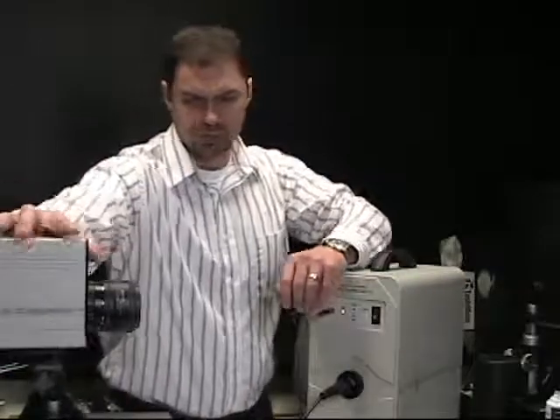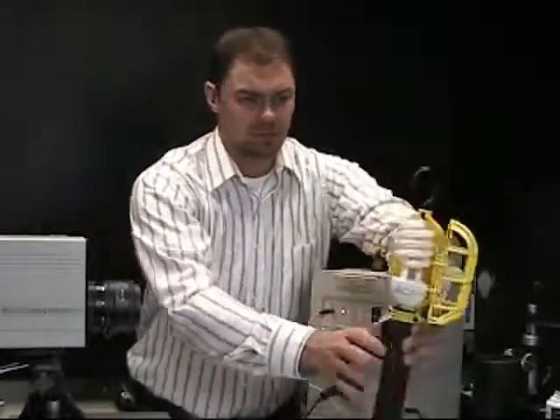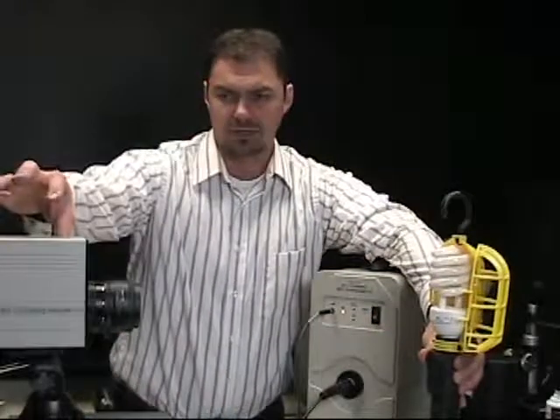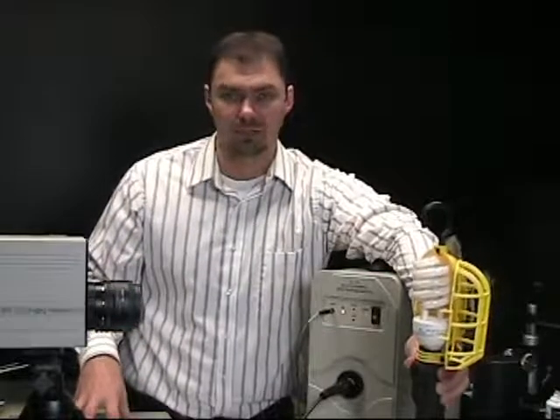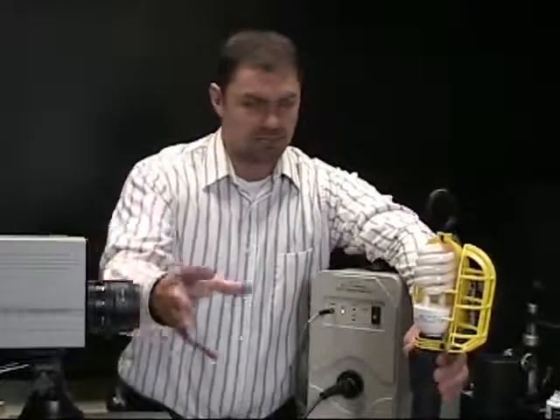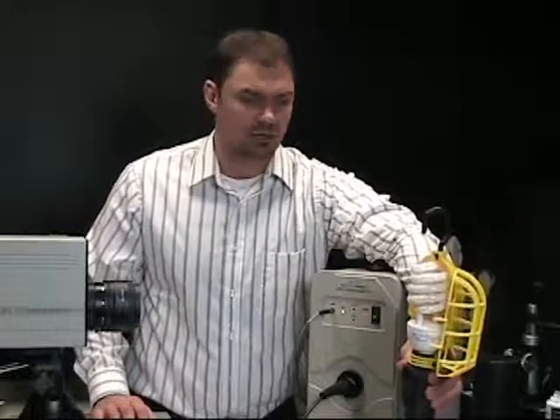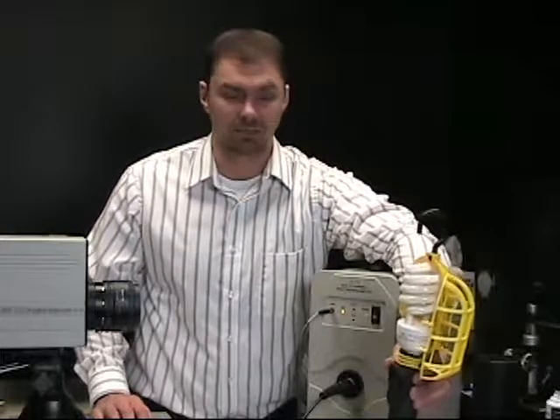So what you're going to do is set up your system with your lamp in a holder again. You're going to be looking through a focusing optic as opposed to using a CCD imaging telescope to align it. But I'll move into the software and I'll show you some screenshots of what it would look like if you were to look through the imaging optic in the 730-9Q that you were quoted. And you would essentially align this, put your dot on wherever you want to measure the radiance, and move into the software. And we'll do that right now, move into the software and show you exactly how you would perform the radiance measurement.